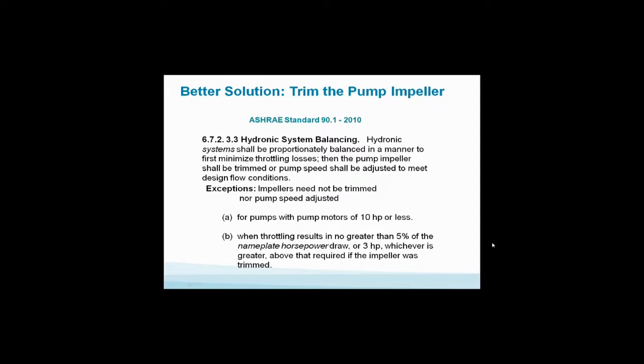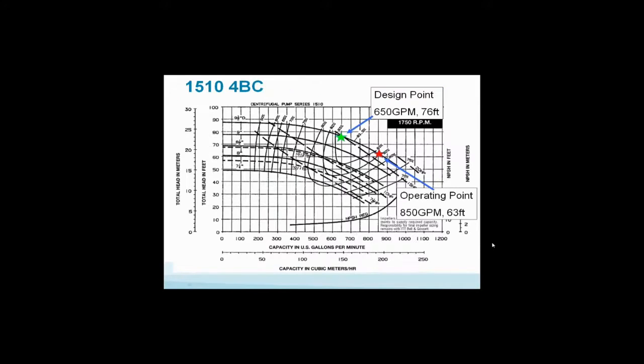So what does ASHRAE 90.1 2010 have to say about this one? Take a quick look. Hydronic systems shall be balanced proportionally, and impellers shall be trimmed or the pump speed adjusted or variable speed drive to meet the conditions. There are some exceptions, 10 horsepower or less, and there's some exceptions about the savings, but in this particular case, we're going to easily have to do it. And I'm going to tell you, most jobs need this done. So how are we going to go about this?